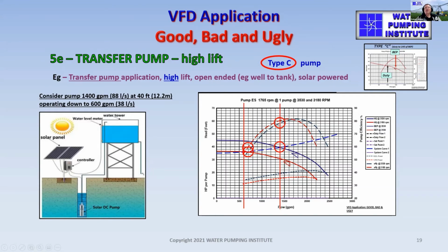And here we're already seeing at peak duty, the efficiency point is already on the downside from the speed curve, and by the time it gets to the lowest output, we're well down into the 50%, and I'd call that ugly. That's a bad application. So as soon as you start applying a VFD to interesting applications, you really have to look critically at your pump configuration before you start to know what you're going to finish up with in the end.